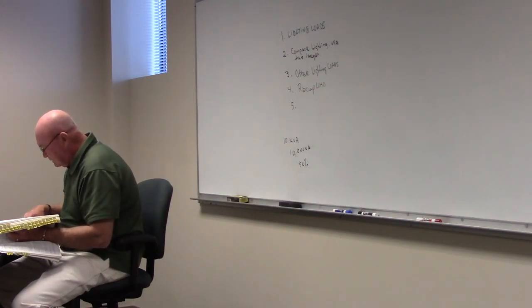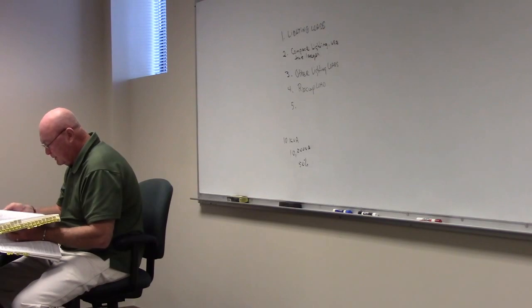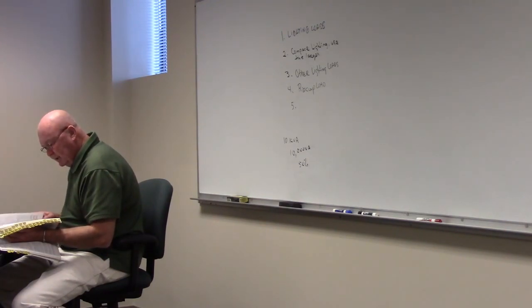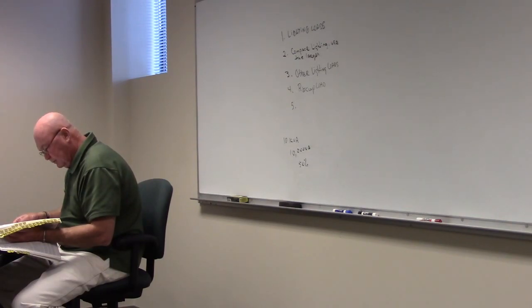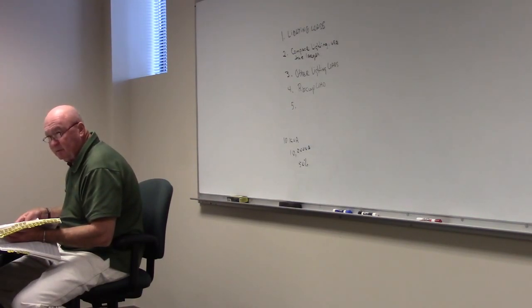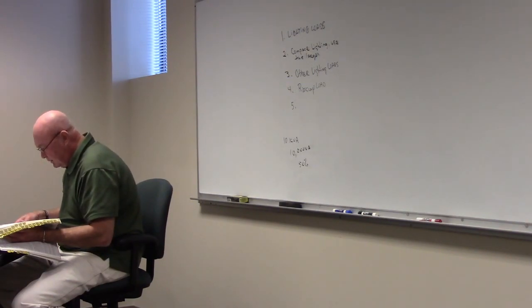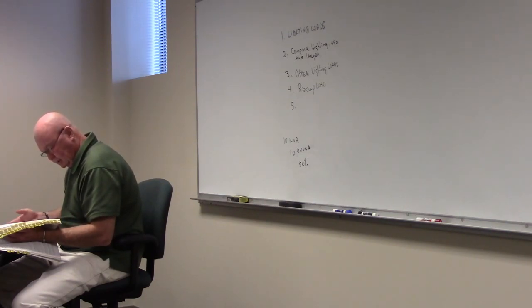Okay. And then lastly, 695, which is a fire pump. Very important. What's one thing we do with a fire pump? What's one of the things about a fire pump that you really need to know? Has its own service. Because the last thing we want the fire pump to do is what? Cut off. But it has its own service. Usually maybe from the same transformer as your incoming power for the building, but definitely not on the same breaker, is it? Has its own meter, doesn't it? On power.